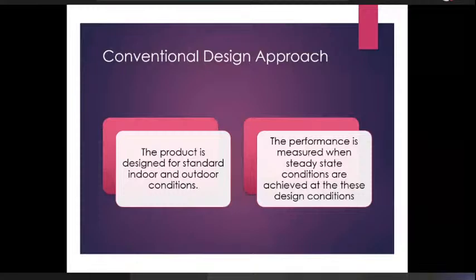So when we look at a product designed for standard conditions, we take it to a balanced ambient calorimeter, we verify the number, and then we are done with it. However, when we have something which is not at one condition but at varying conditions, then we need a different standard. And that standard was created and evolved later. So that becomes a tool to show the advantage of a variable speed system versus a fixed speed system.